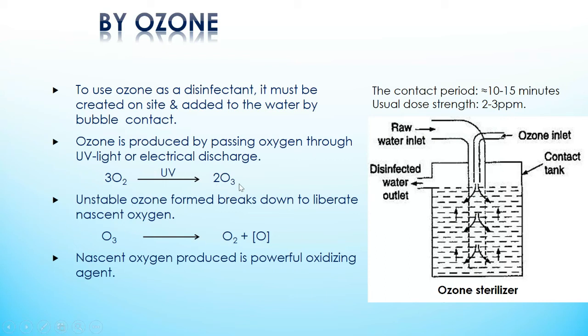For carrying out the disinfection, ozone is released into water in a sterilization tank. The contact period is about 10 to 15 minutes. As ozone is passed into water, because of its unstable nature, it breaks down producing oxygen and nascent oxygen. This nascent oxygen is a very powerful oxidizing agent which kills the bacteria and also oxidizes the organic matter present in the water.